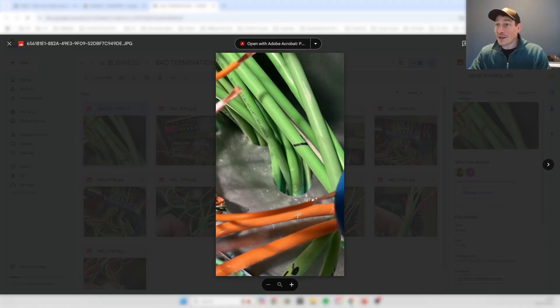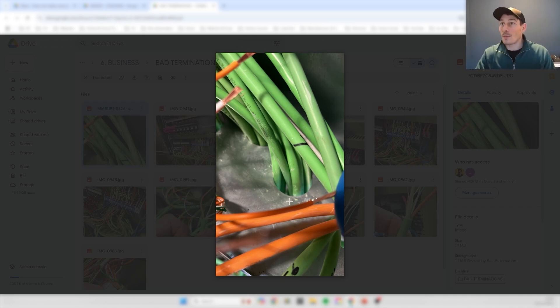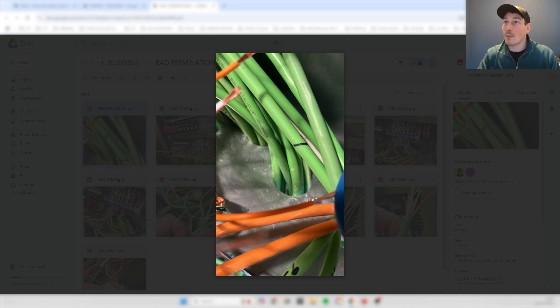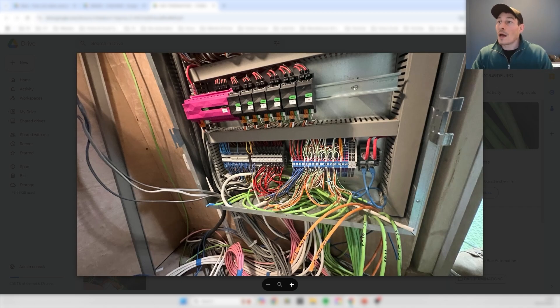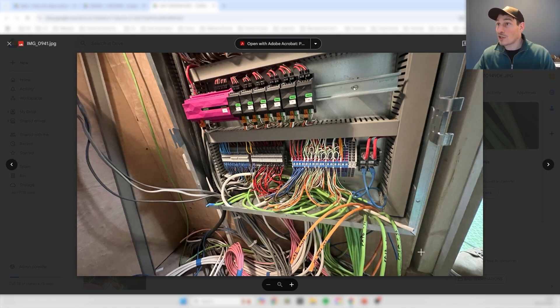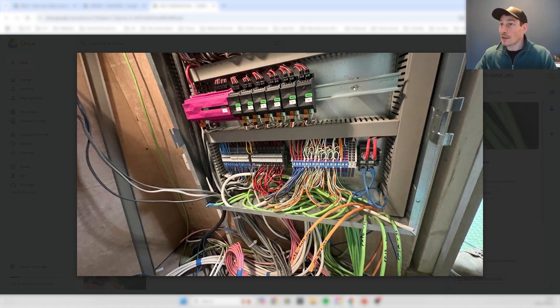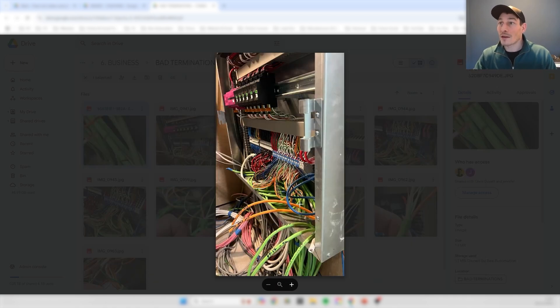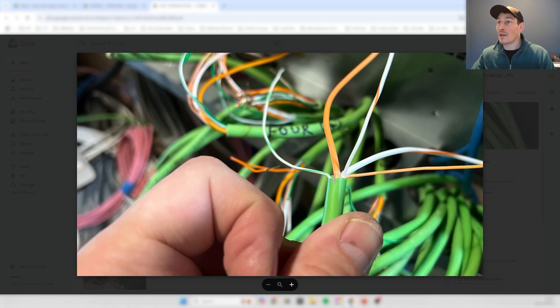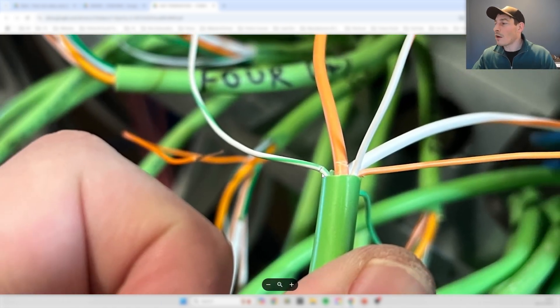Here's why — this is disgraceful. Any electrician should know there should be grommet strip around here. This was done by a qualified electrician with a lot of experience — and that's unacceptable. When it comes to dressing cables into the panel, they're just throwing them in. You spend hours building a really nice tidy panel and then the final terminations are slung in incorrectly.